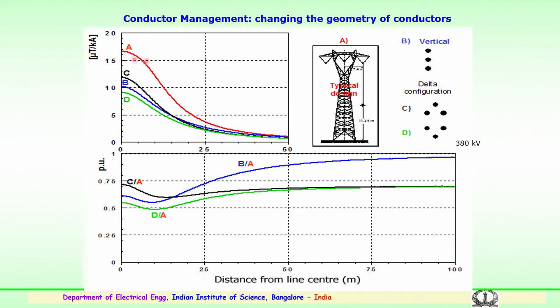So, for various current ratings in terms of kiloamp, the micro tesla, that is the magnetic field, is estimated. And you see that particularly for this configuration, the magnetic fields are higher, and going in for either a vertical, a delta, or an inverted equilateral triangle arrangement of the conductors could lead to better performance of the line, and also the magnetic fields getting reduced. So, this is how it is shown here, and this gives the per unit values versus the distance from the center.